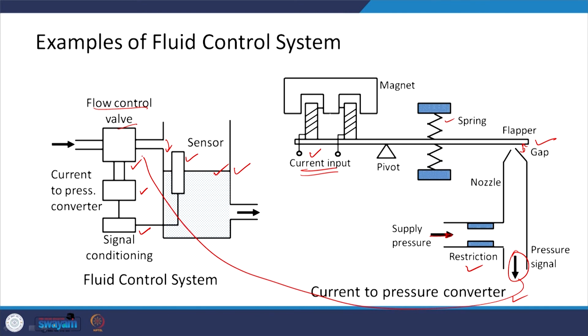The current to pressure converter could look something like this. You have the current input here, okay, there is a pivot and there is a spring here and there is a flapper here. Okay. So, you could have a restriction here, you supply a pressure through a restriction, okay, and based on the gap over here which is maintained with the help of the current input here, you could have the pressure signal, okay, and this signal can be used here to control the flow.